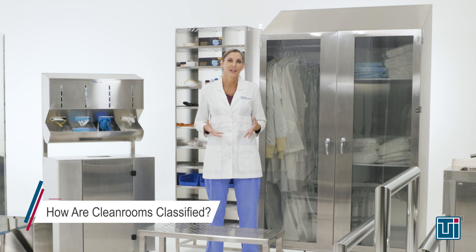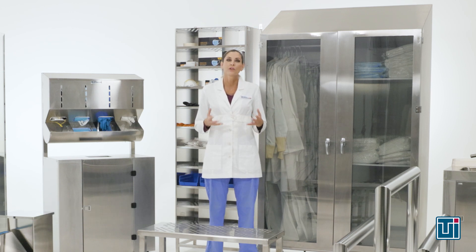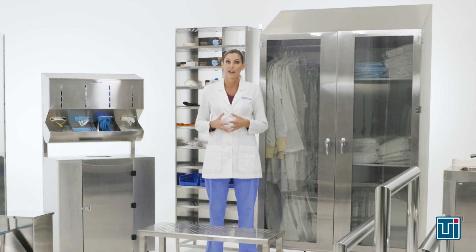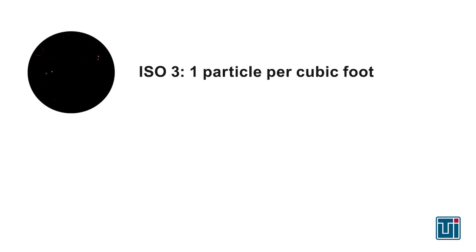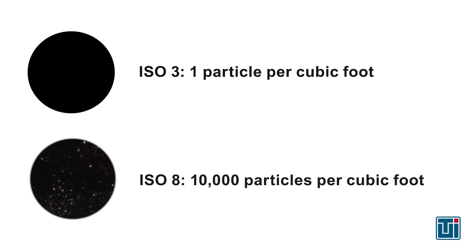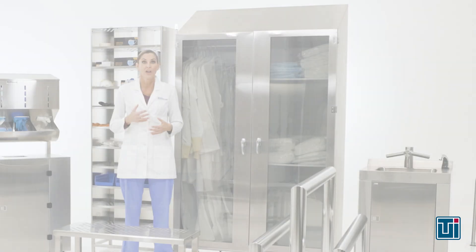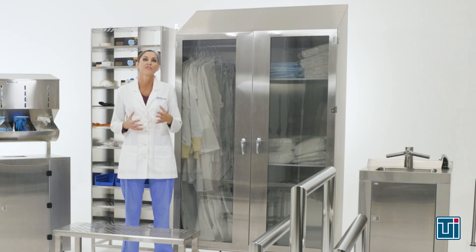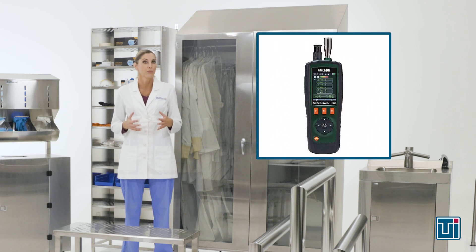How are clean rooms classified? The International Standards Organization, or ISO, categorizes clean rooms based upon the quantity of particles per cubic foot of air. The cleanest classification, ISO 3, denotes an environment containing one particle per cubic foot. The least rigorous classification, ISO 8, specifies an atmosphere containing 10,000 particles per cubic foot.